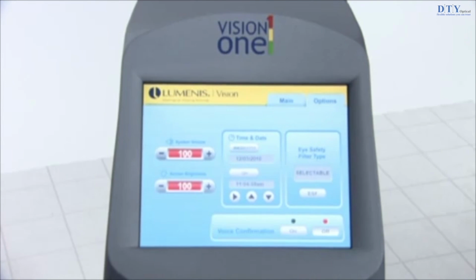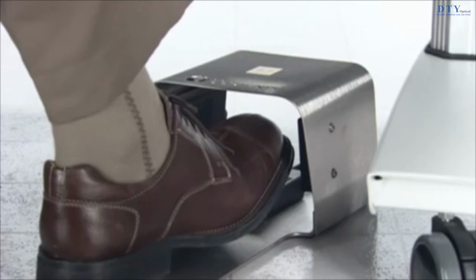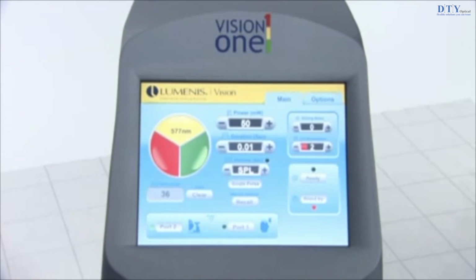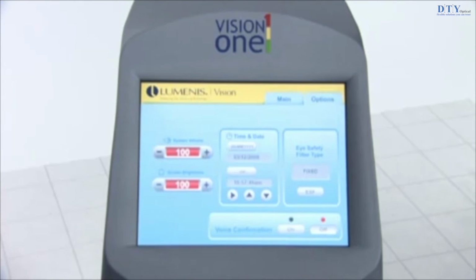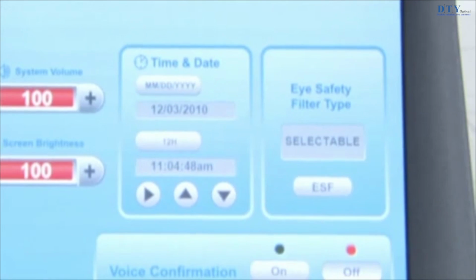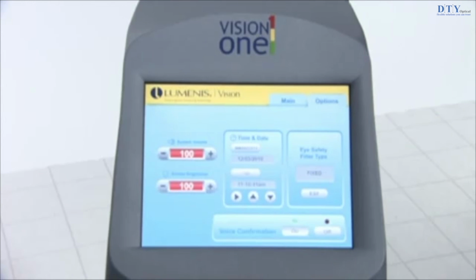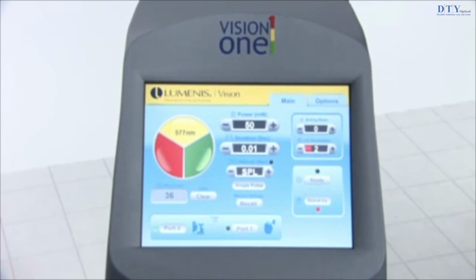Selectable. The eye safety filter moves into position when you place the laser in ready mode, also available only with automatic eye safety filters. Smart selectable. The eye safety filter moves into position when you place your foot inside the smart foot switch housing while the laser is in ready mode. Functionality available only with automatic eye safety filters and the smart foot switch. To select the eye safety filter mode, press the Options tab to view the option screen. Next, press the ESF selector until the desired eye safety filter mode displays. Press the Main tab to return to the treatment screen.